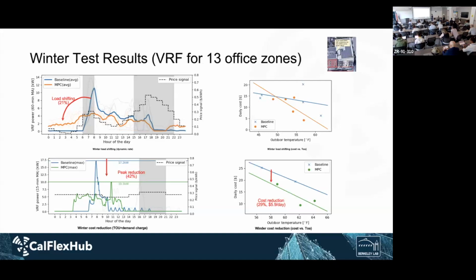The bottom is another trial, testing a different signal: the time-of-use signal. The dotted line is the price signal, and although it has TOU, it's pretty flat. In that part the MPC isn't doing much, but there's a demand charge, so by coordinating multiple VRF indoor units, turning them on and off and alternating their operation, we can reduce the peak demand. The demand savings give us a pretty big cost reduction, about 30%.